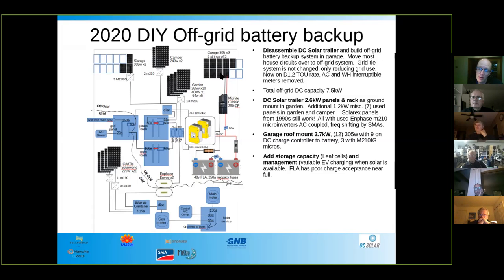On the garage roof is a very short run, only 15 feet of conduit from underneath the panels straight down to this charge controller and right into the battery. It would be kind of impossible to use this type of charge controller for panels that are way off down in the garden or at the other end of the house without really long DC runs.